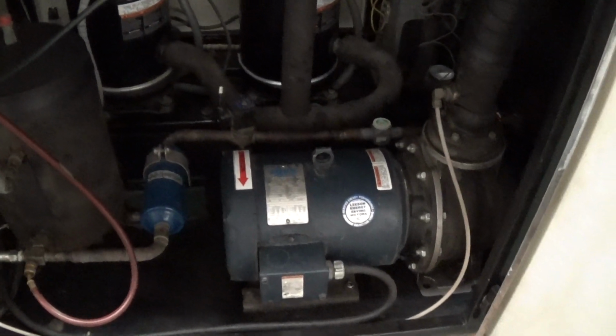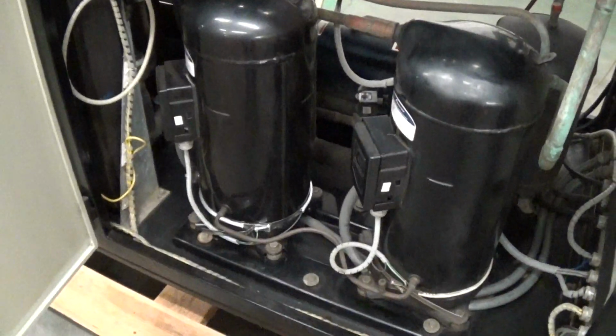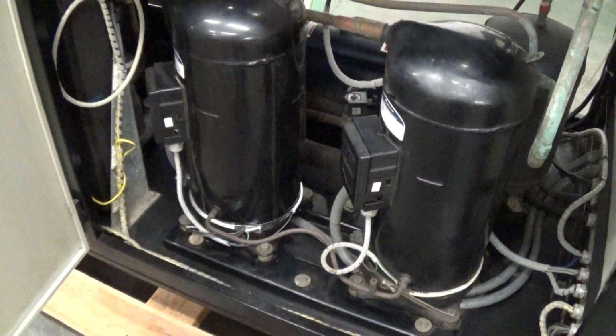In the bottom section here, you have your 5 horsepower pump, the refrigeration receiver I just talked about, and your 2 scroll compressors. I'll go over the other side here. We repainted some of the doors. We also got some new latches. Here's another view of your compressors. These have heater bands on them, and the heater stays active as long as you have live power coming into the chiller. And it's nice to keep live power on all the time to keep the refrigerant and the compressors from getting too cold.